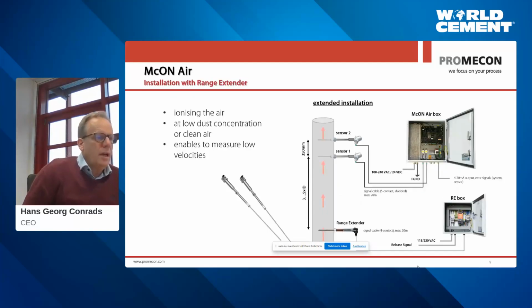Now, I'm showing you something else which is probably not so relevant for your plant. What happens if you don't have dust? For example, what if you have absolutely clean air and clean gas? Then in this case, we have a range extender that can ionize the gas. And this ionization allows our system to measure the flow the same way as if there was dust in the gas, right? This is something that we usually use for batch applications, or in power stations where you have clean air going through the mills.